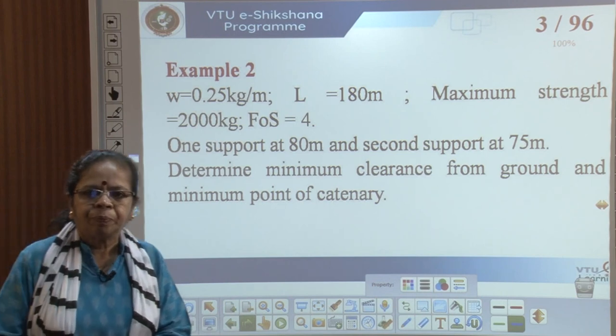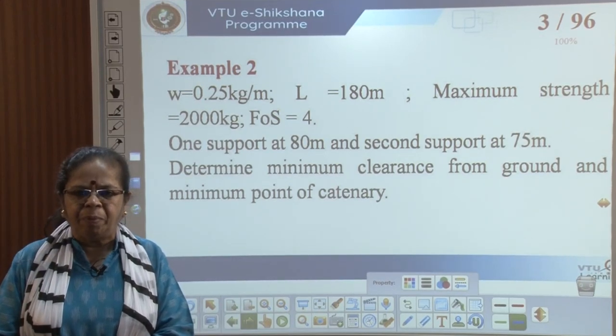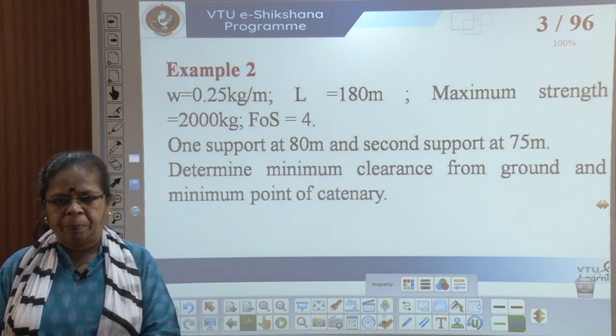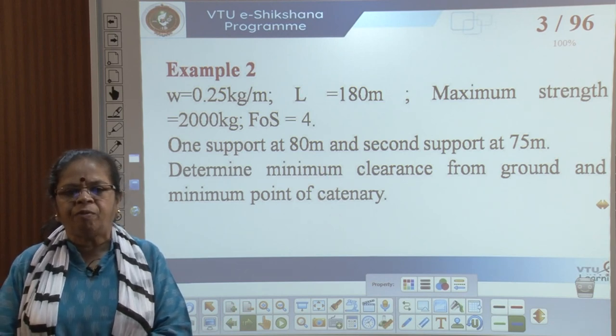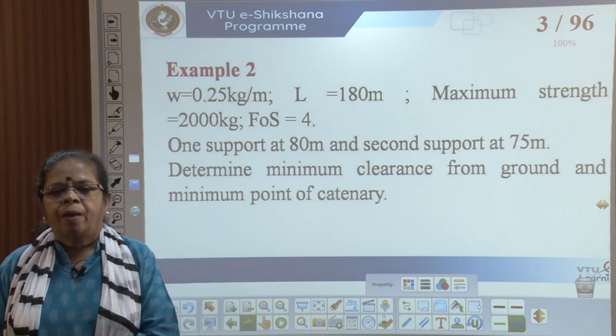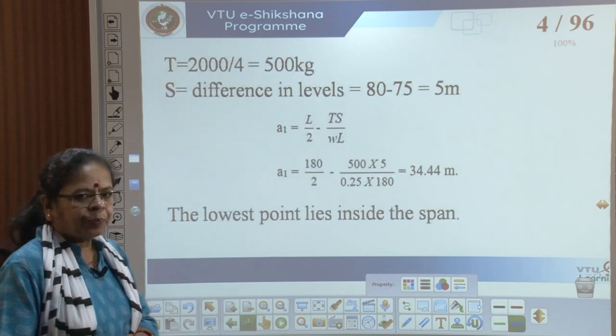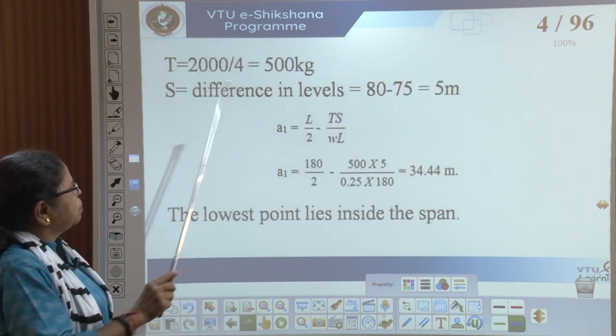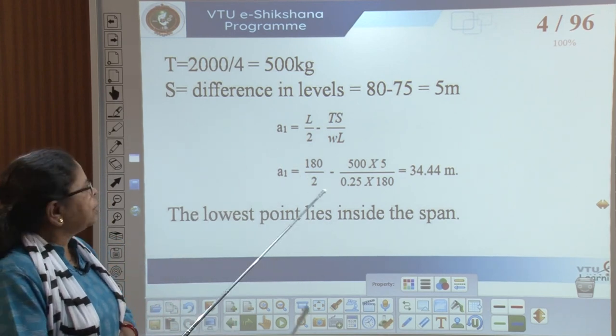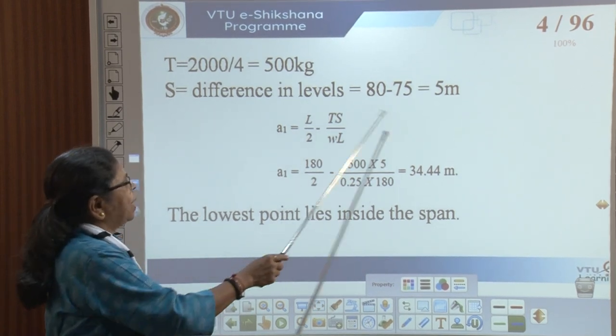Let us consider the second example. The weight of the conductor is 0.25 kg per meter, the span length is 180 meters, the maximum strength is 2000 kg, and the factor of safety is 4. One support is at 80 meters and the second support is at 75 meters. You have to determine the minimum clearance from the ground for the conductor and also the minimum point of catenary, that is point O. The tension is 2000 divided by 4 = 500 kg. The difference in the support levels is 5 meters.